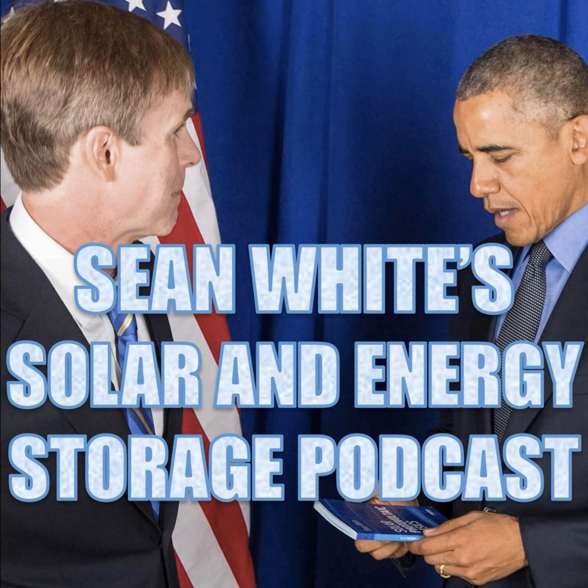What we're doing is going to one place in the NEC and it always sends you to another place. So when you're in Article 706, that does not mean other things don't apply. You can't just install an energy storage system by only looking at Article 706 - you have to look at the whole rest of the National Electrical Code, specifically Chapters 1 through 4: Chapter 1 General, Chapter 2 Wiring and Protection, Chapter 3 Wiring Methods, Chapter 4 Equipment for General Use.